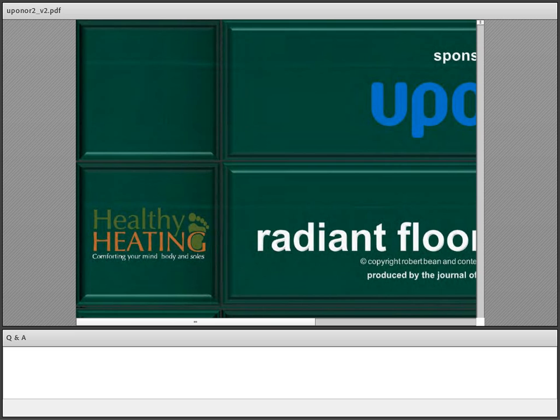And of course, if we can influence the health of the environment, then by connection we can influence the occupants. The nice thing about these hybrid systems is that there's no confusion: the heating system isn't confused about having to do dehumidification or humidification at the same time as space heating or cooling. We have a system dedicated strictly to the thermal comfort component of the occupant, and another system dedicated to respiratory comfort. This is, in fact, how our biological systems work from a physiological point of view, as we'll explain, and it also reflects in codes and standards.